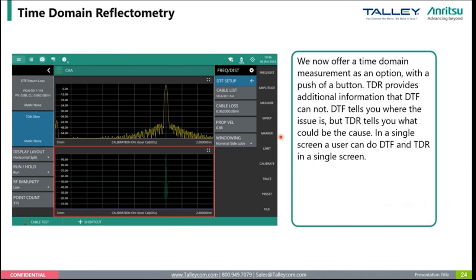This allows you to get much more information about the cable antenna analyzer measurement. Traditionally, when you did DTF, distance to fault, it gave you a location of the fault, but you had no real idea of its nature—was it open, was it short? It wasn't very clear. What TDR does, measuring in ohms, tells you how bad it is: was it open, is it short, and how far is it from what it's supposed to be?